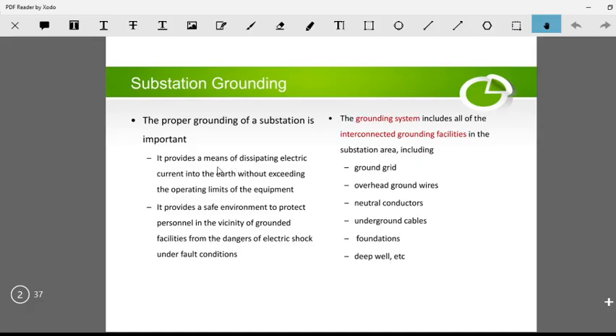That's one purpose. The other purpose is to provide safety to the personnel working in the substation. Make sure that if anybody touches anything, like the chassis of a transformer or a tower, there won't be any excess current flowing through the body, which could damage the worker. So those are the two purposes for substation grounding.